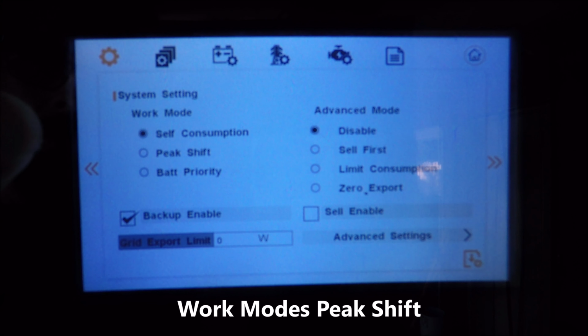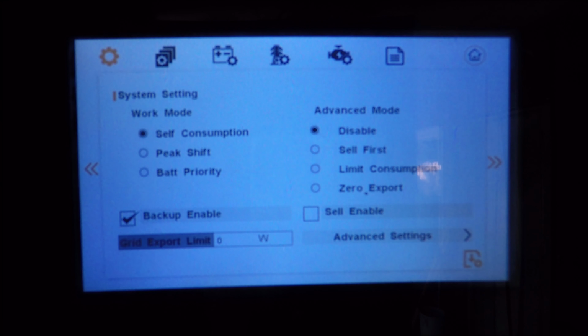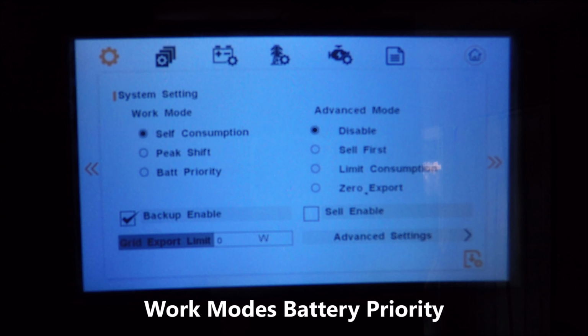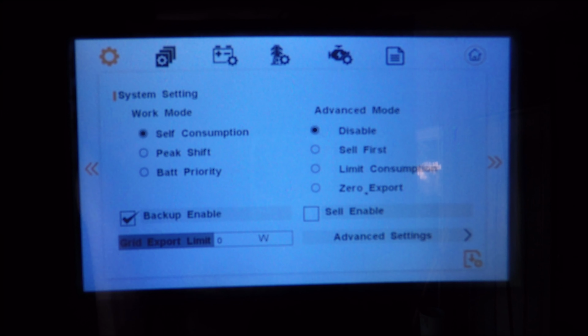Peak shift, just to go over the other options here: if you have peak and off-peak rates, you can set those times here. For instance, you could charge your batteries in the off-peak times at the low rate and use the batteries during your peak times, which would be a higher rate. Battery priority prioritizes keeping the batteries charged to be available when the power is off and solar is unavailable. If the batteries are 100%, they will power the loads. Make sure backup enabled is selected to ensure if the power is off that the inverter will use the battery to power your loads. We're going to move over to the advanced mode.